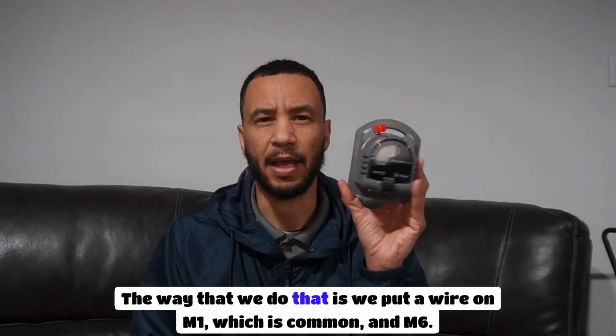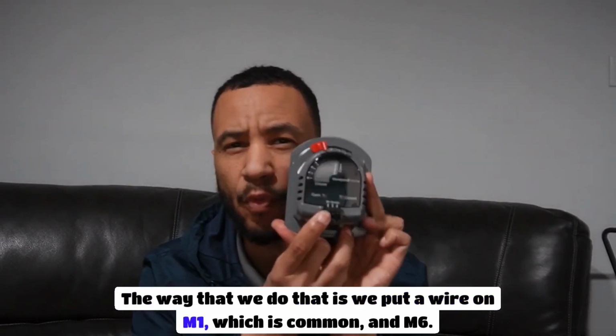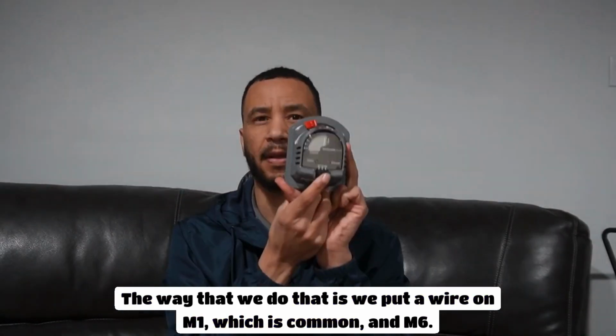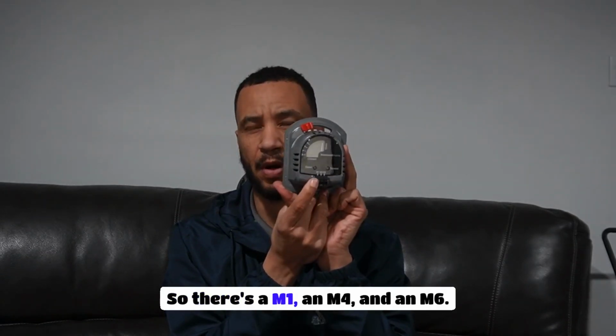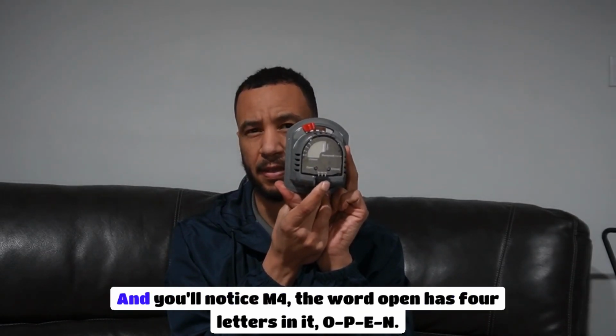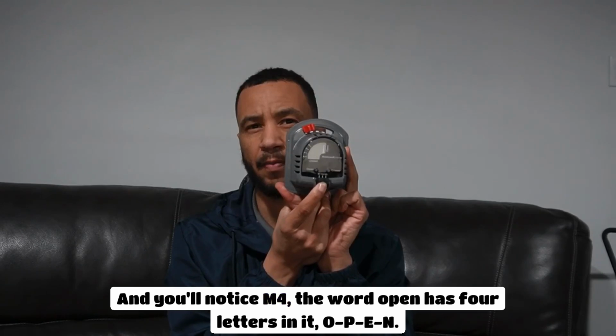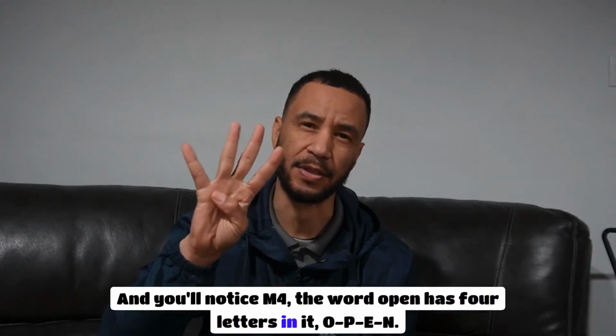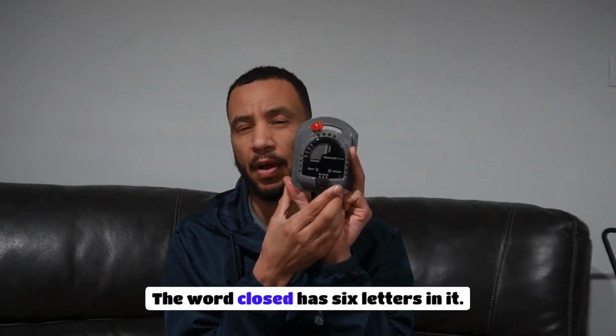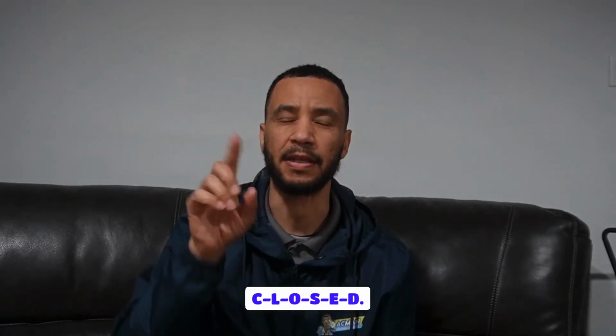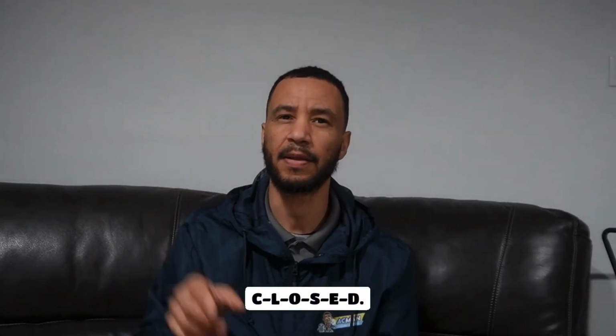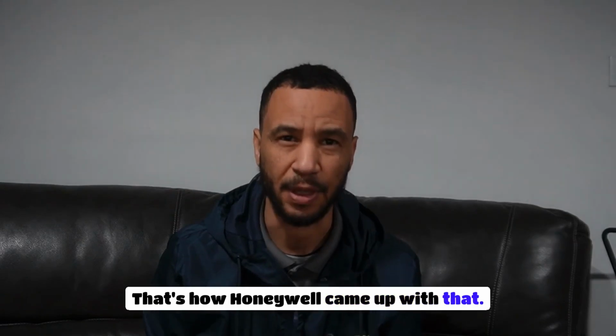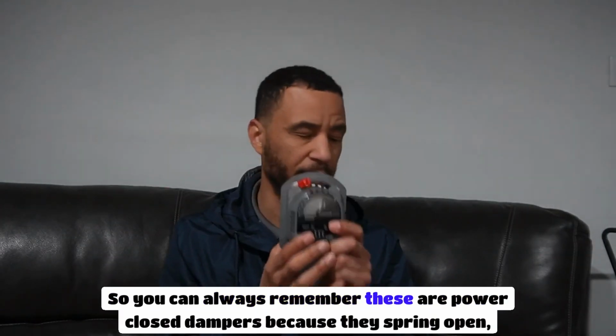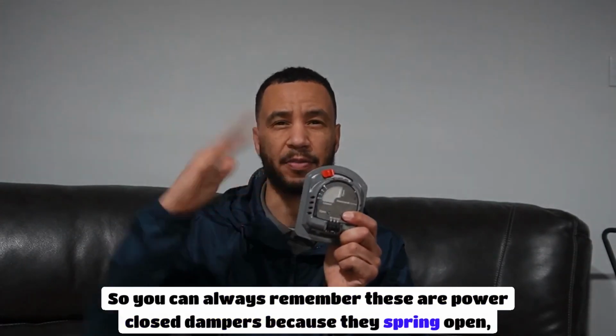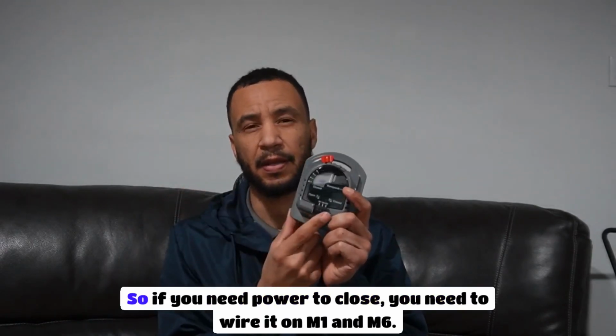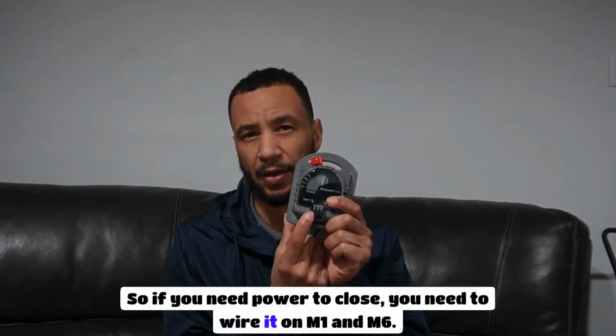The way that we do that is we put a wire on M1, which is common, and M6. So there's an M1, an M4, and an M6. And you'll notice M4, the word open has 4 letters in it, O-P-E-N. The word closed has 6 letters in it, C-L-O-S-E-D. That's how Honeywell came up with that. So you can always remember these are power closed dampers because they spring open, they need power to close. So if you need power to close, you need to wire it on M1 and M6.